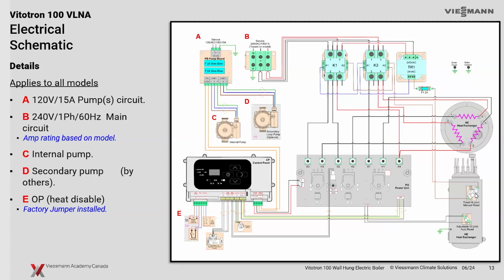If the fixed high limit opens up here, it's going to open up the contactor power here so that we lose the 240 volt directly into the triac board itself. So there's your safeties sitting on that side. But just to mention that there are two different power sources from A and B here. Electricians run an extra neutral with that 240 volt. They could possibly split that with a neutral to give you a 120 volt and a neutral off of that 240 here. You'd have to talk to your electricians about how all that would work. And of course you have to make sure you have separate circuit breakers for those as well, or fuse protection.